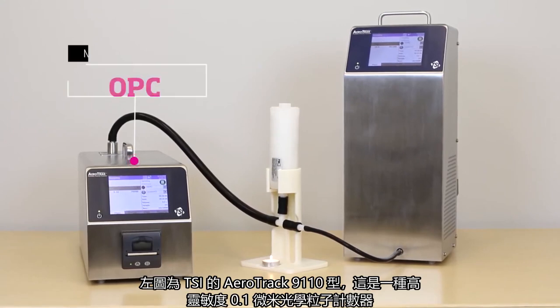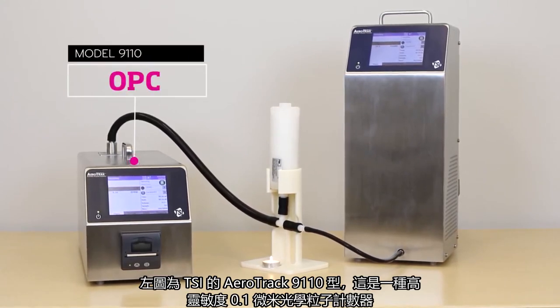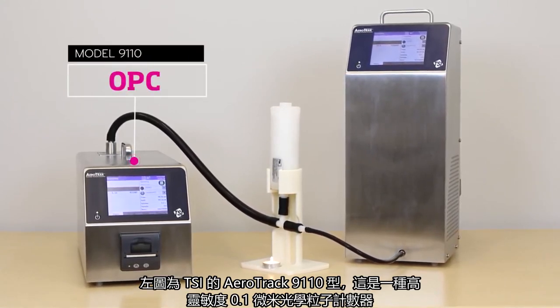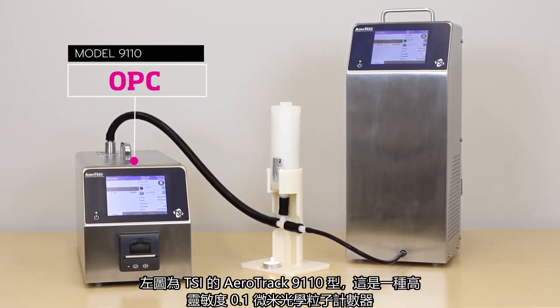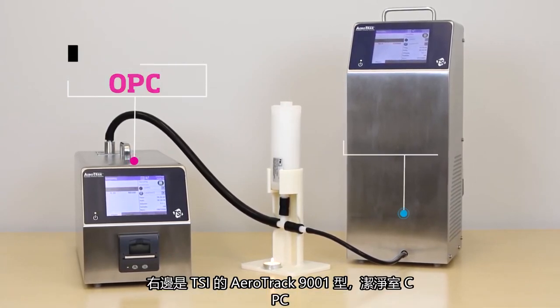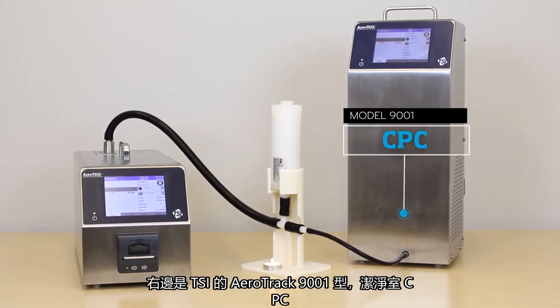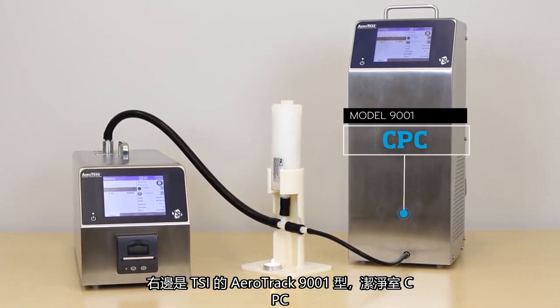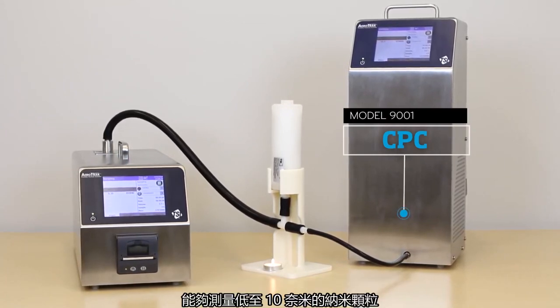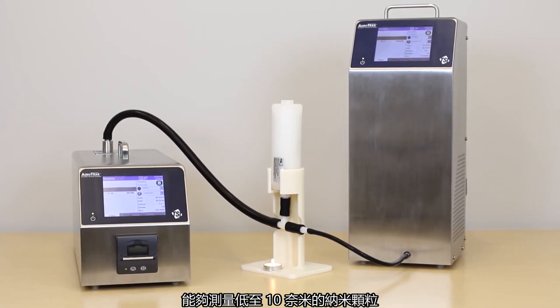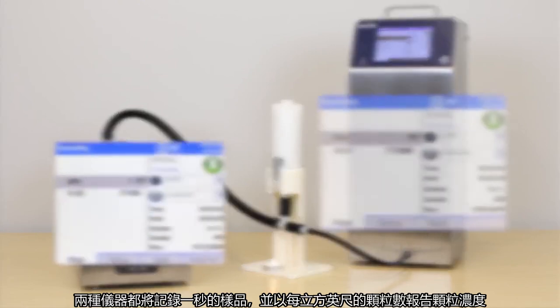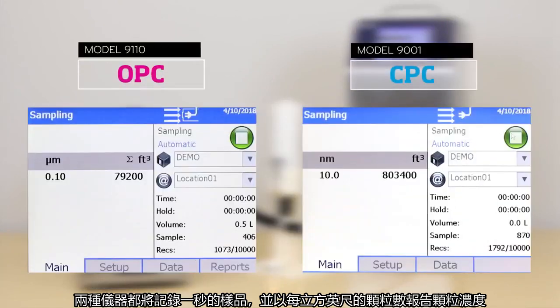On the left, TSI's AeroTrack Model 9110, a high-sensitivity 0.1 micron optical particle counter. On the right, TSI's AeroTrack Model 9001 Cleanroom CPC, with the capability to measure nanoparticles down to 10 nanometers. Both instruments will record 1-second samples and report particle concentration in particles per cubic foot.